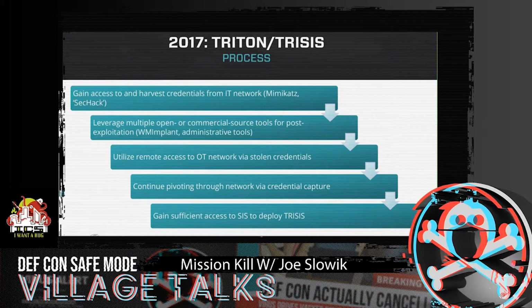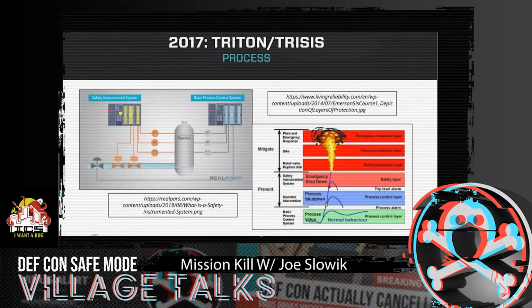And that's an interesting part and requires us to understand what a safety instrumented system is within the context of industrial operations generally and petrochemical facilities specifically. Because safety systems, while they don't ensure that nothing bad ever does happen, a safety instrumented system typically acts as sort of an emergency control system in parallel to the basic or operator controlled environment, such that in the event of a hazardous or dangerous set of conditions within the plant environment, automated controls are put into place to ensure an easier or less physically disruptive recovery of the plant environment to minimize damage, disruption, and facilitate recovery.